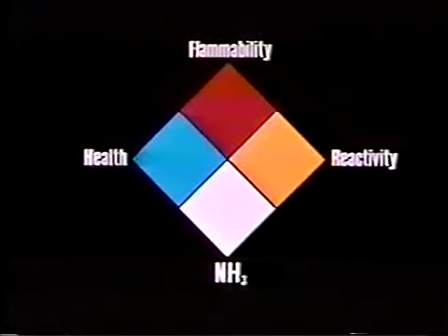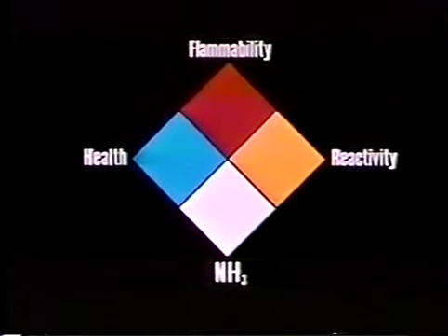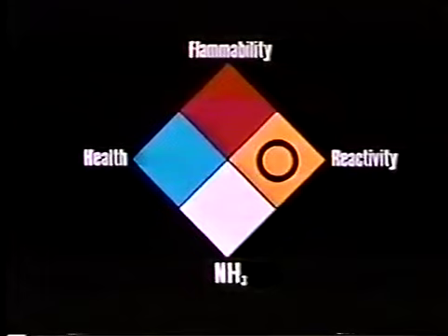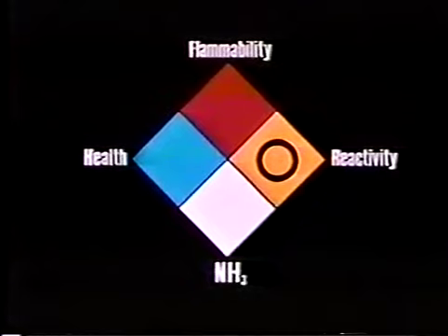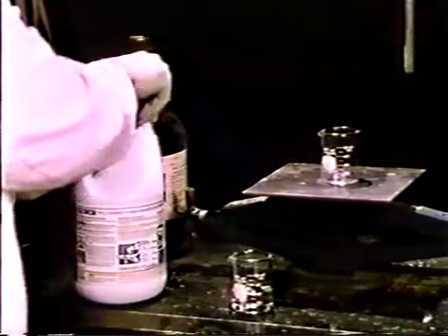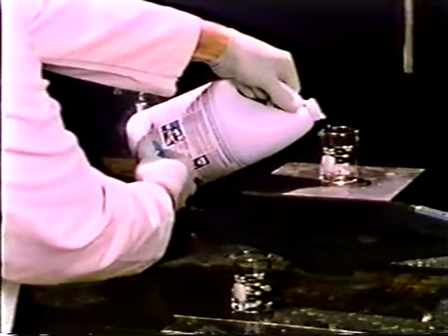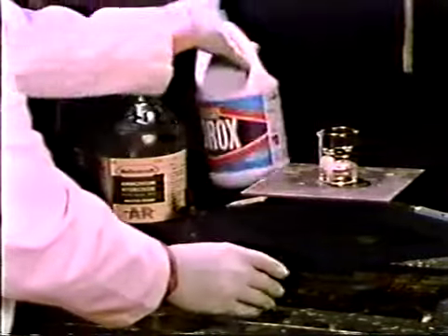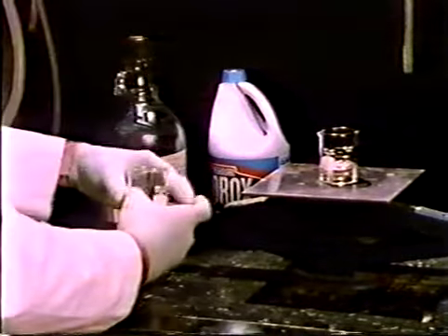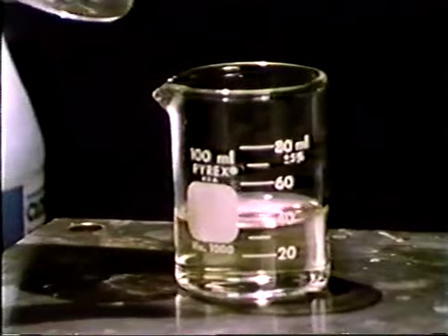In NFPA 49, hazardous chemical data, the reactivity hazard for anhydrous ammonia is listed as zero, indicating a material which is normally stable and not reactive with water. Yet anhydrous ammonia will react with many substances. One reaction can be demonstrated by combining two common household products — ammonia and chlorine bleach. The result is nitrogen trichloride gas, which is extremely sensitive and explosive.